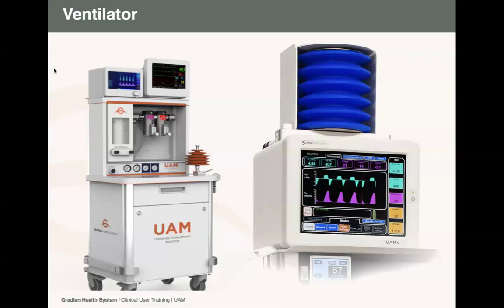But yes, thank you, Maria. But also in summary, of course, that's the slide we are discussing. We said there are steps which will be done before, things like selecting weight, setting parameters, how much the volume, how much is the total rate, and all of those. We were emphasizing more on the steps for you to start the UMV. If you start the UMV when the isolator switch is on the bag side, the machine will give some alarms. So that's what we are saying. Always, before starting the UMV, make sure you switch the bag isolator switch to the vent side, and then you start your UMV. When you are weaning the patient, same thing.